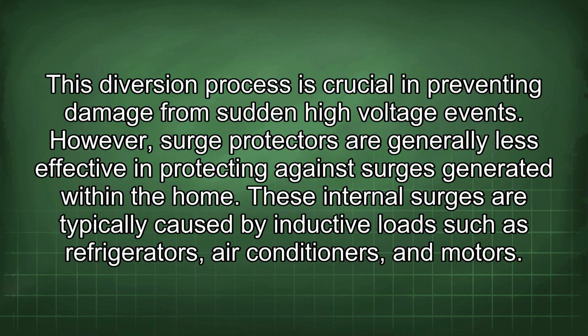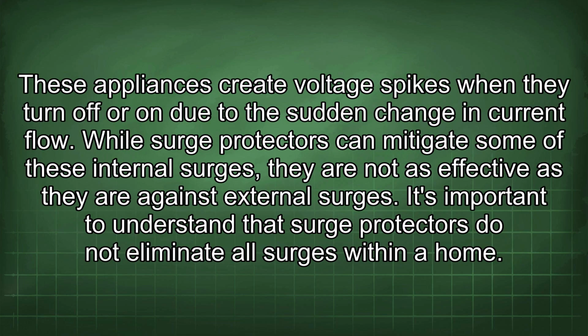However, surge protectors are generally less effective in protecting against surges generated within the home. These internal surges are typically caused by inductive loads such as refrigerators, air conditioners, and motors. These appliances create voltage spikes when they turn off or on due to the sudden change in current flow. While surge protectors can mitigate some of these internal surges, they are not as effective as they are against external surges. It's important to understand that surge protectors do not eliminate all surges within a home.